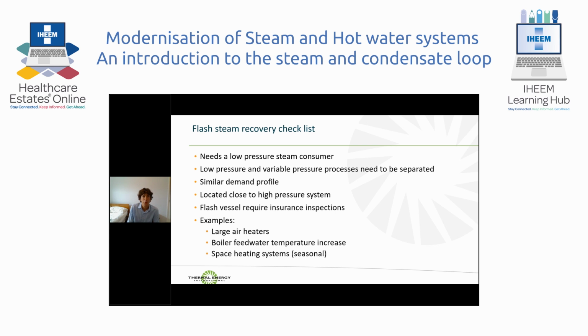Flash steam recovery is a great opportunity for many sectors. What we need to go through is this checklist to make sure whether it's suitable for your plant. We need a low pressure steam consumer. We need to be able to effectively separate low pressure and variable pressure processes, those with control valves, from the condensate return system that feeds to the flash vessel. We also need a similar demand between the generation of flash steam and the consumption of low pressure steam. Ideally, that's located close to the high pressure system, to the flash vessel, because low pressure steam has a very high volume and therefore needs large diameter pipes to transport it. In the hospital environment, most of our steam is actually being used for generating hot water, which reduces the opportunity for flash steam recovery.